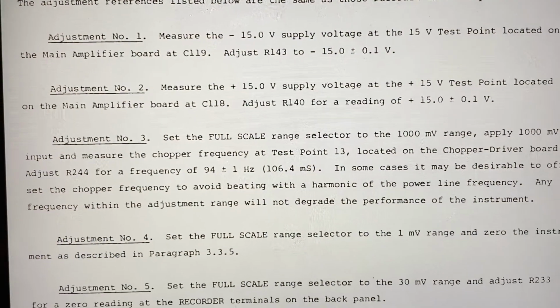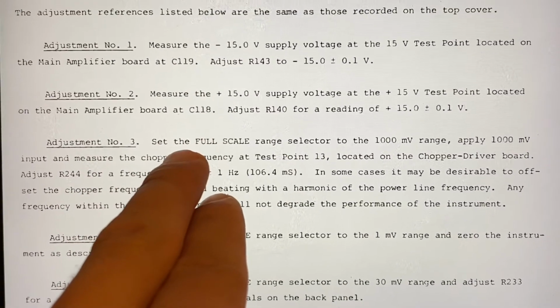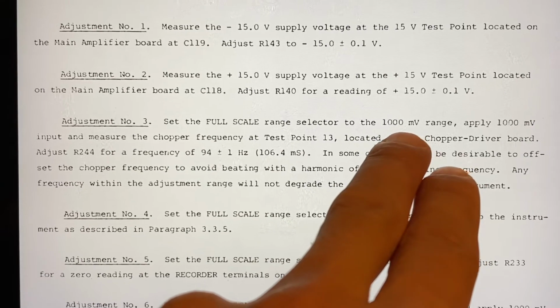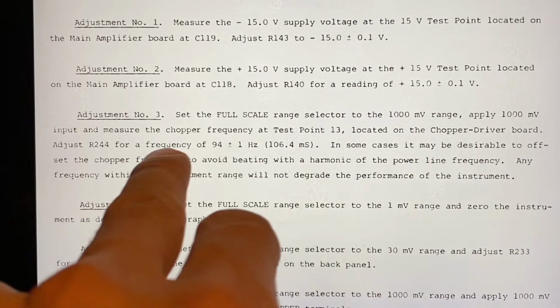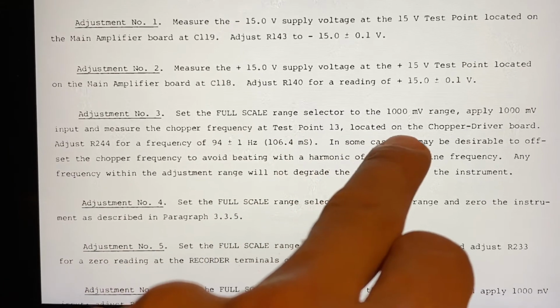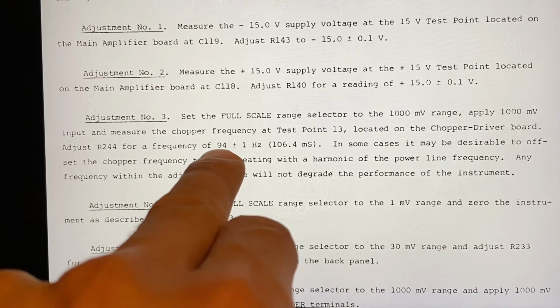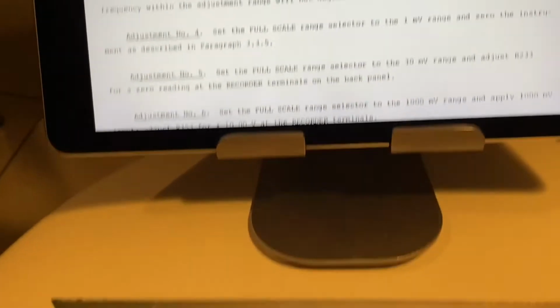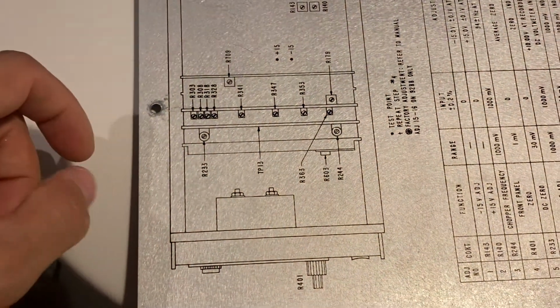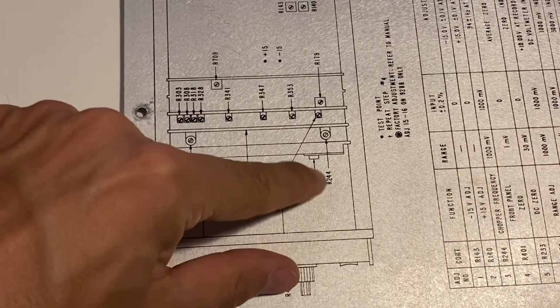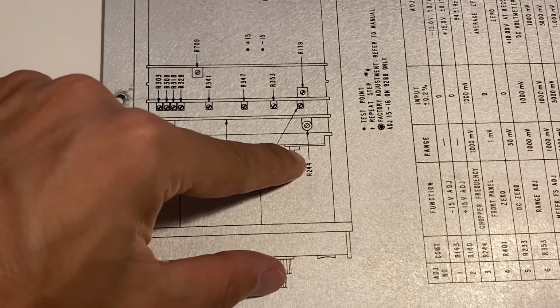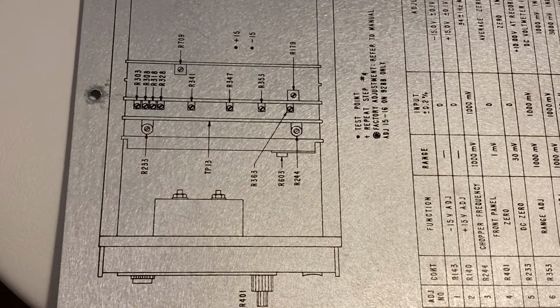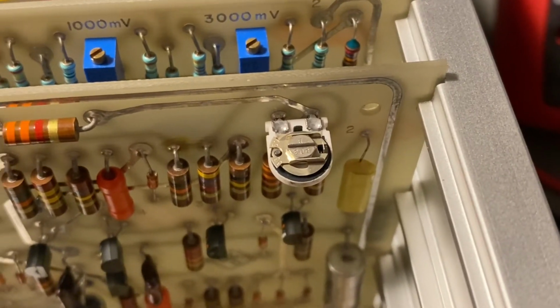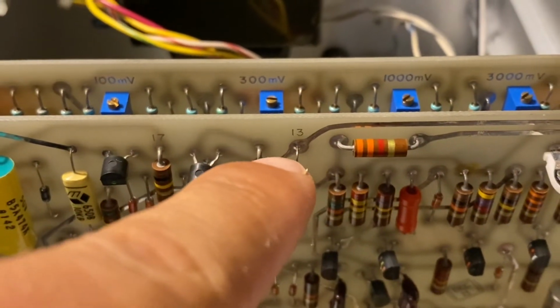Now we go to the third step, which says to set the range to the 1000 millivolt range, so 1 volt, and measure the chopper frequency at test point 13, and adjust R244 for 94 plus minus 1 hertz. For R244, we have a schematic here on the inside of the top cover. R244 is this trimmer here on the right. That's R244, and point 13 is this point here.